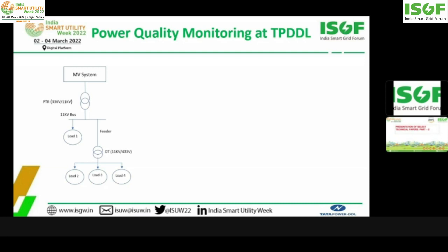And it can be better understood by the help of this diagram. There is a utility supplying to 4 consumers. Consumer 1 is directly connected to the 11 kV bus. And 3 consumers, consumer 2, consumer 3, and consumer 4 are being served by a common transformer. Now, if you are interested in measuring power quality at any of these 3 consumers, consumer 2 or consumer 3, then the PCC point would be LT of this transformer. And now if you are interested in measuring power quality at consumer 1 facilities, then the PCC would be this 11 kV bus from where utility can supply to other consumers also.